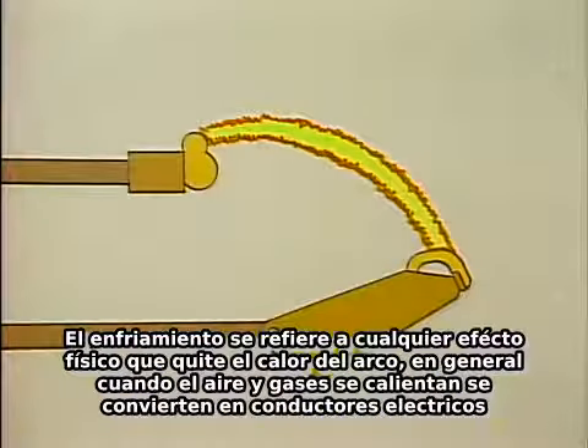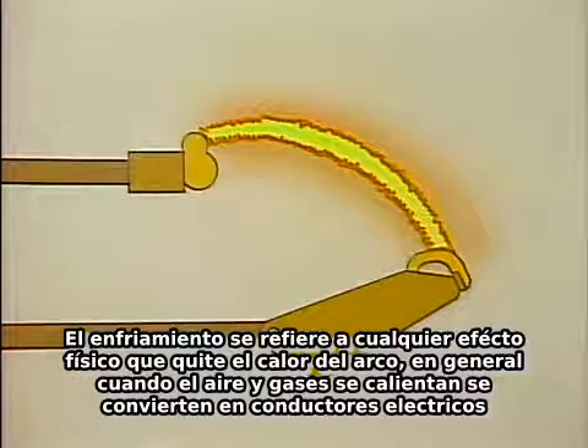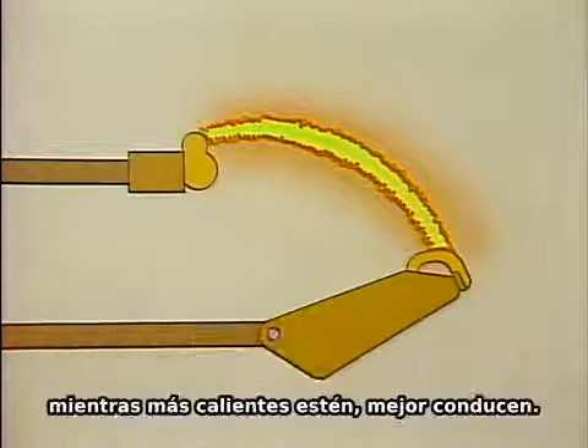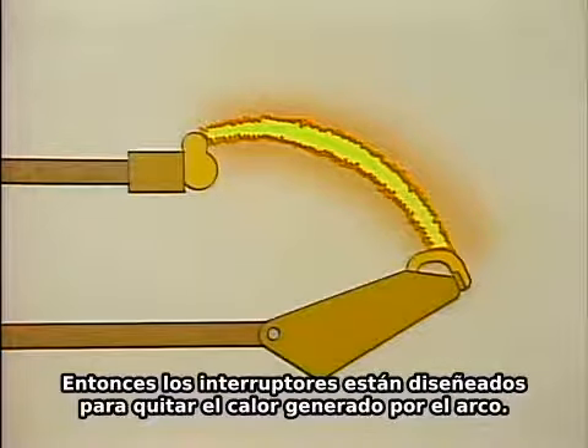Cooling refers to any physical effects that take heat away from the arc. In general, when air and gases are heated, they become electric conductors. The hotter they get, the better they conduct. So breakers are designed to take heat away from the arc.